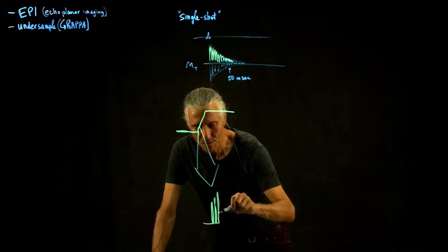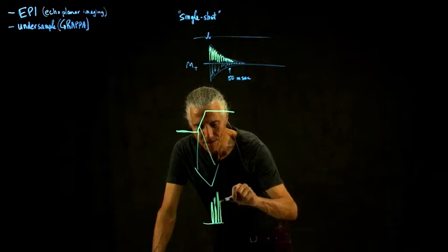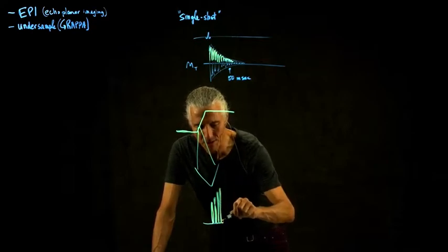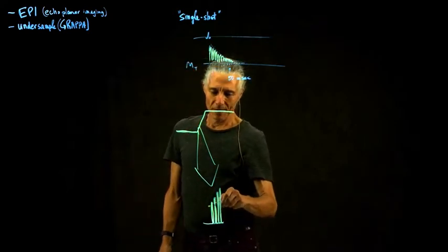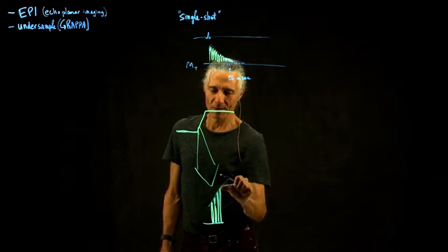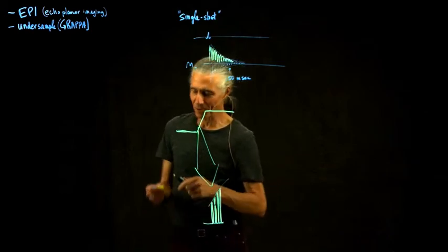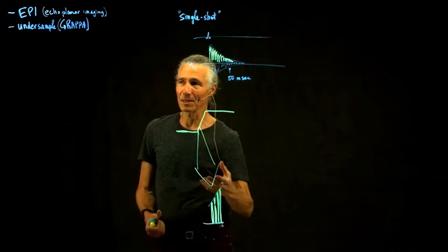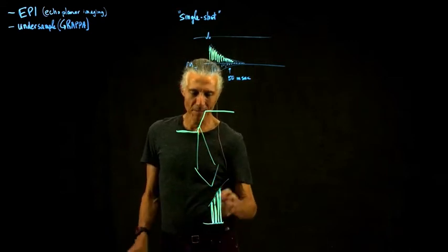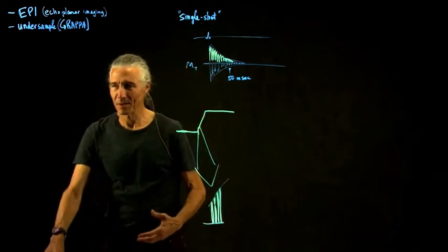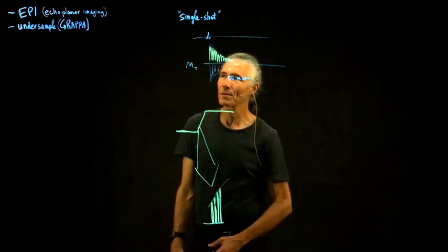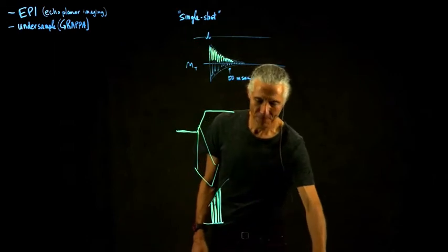So it's actually a switching amplifier. It just uses the transistors as switches and just turns them on and turns them off. And it basically approximates the gradient waveform as a bunch of switches, very powerful switches, because the transistors can switch a lot of current that way. And by doing it this way, they were able to generate these amplifiers that are much more powerful, that will allow you to do EPI.